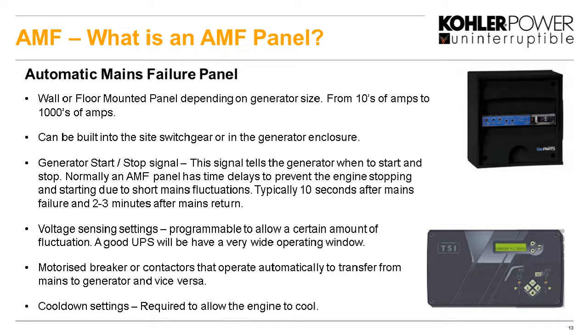So what it's doing is sensing for the voltage from the mains and also from the generator. And when it sees the mains go out of tolerance, which would be programmable, it typically will wait a few seconds, because we don't want the generator to start immediately if there's a dip in the mains. We make sure that the mains is out of tolerance for a set period of time, and then we send a signal to the generator to start and come available. And once it's available, the AMF panel would do the changeover from the bad mains onto the good generator. And during this time, it will always be sensing, looking for the mains to return.